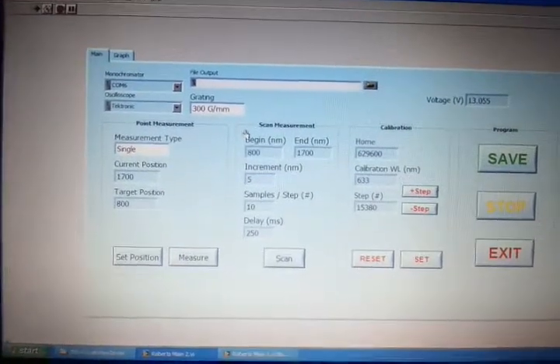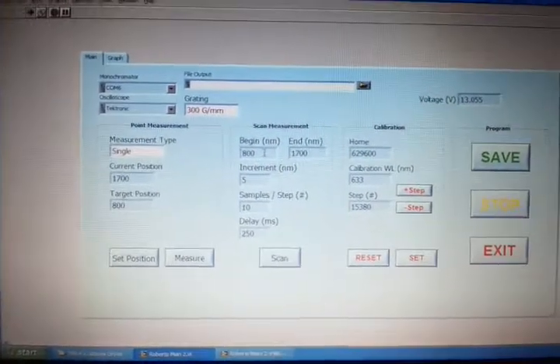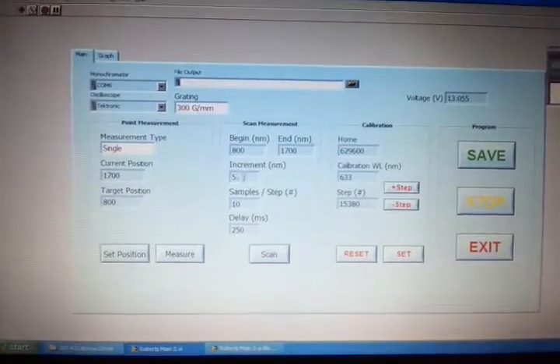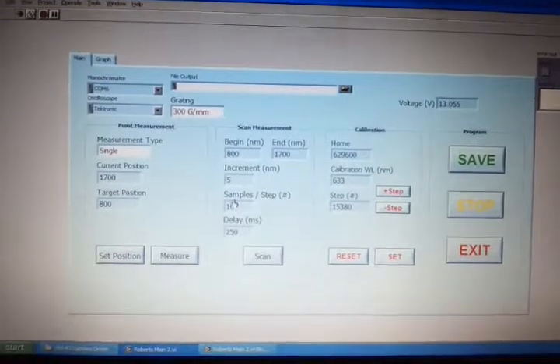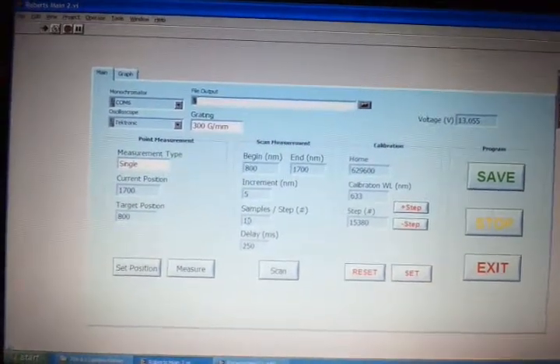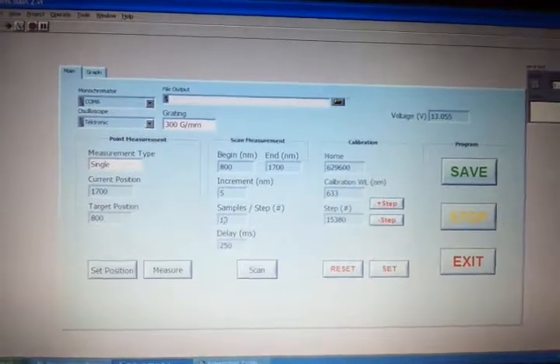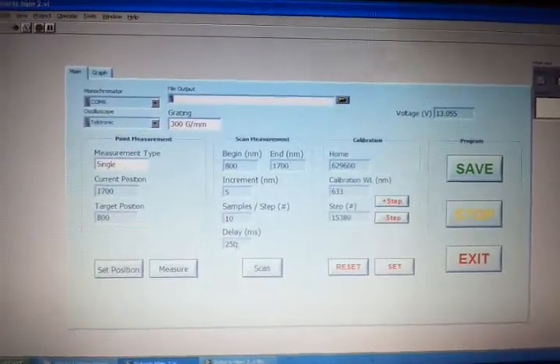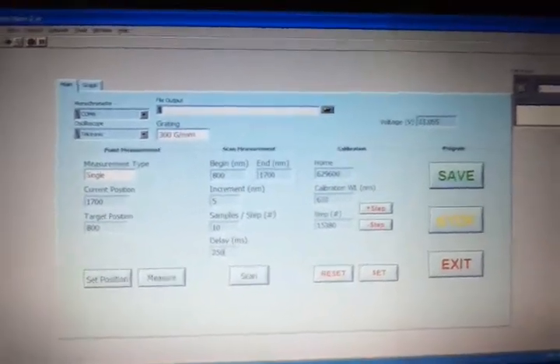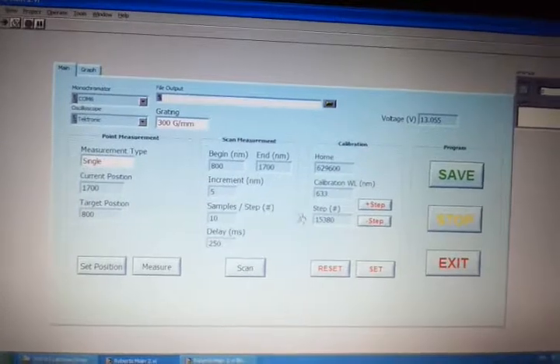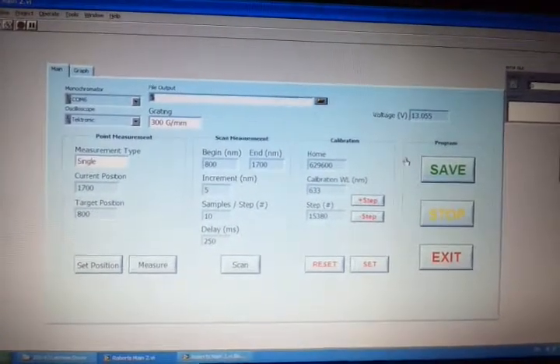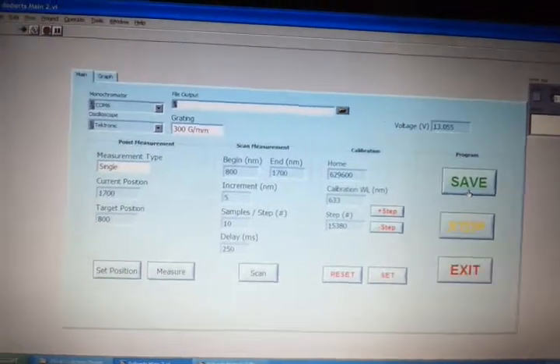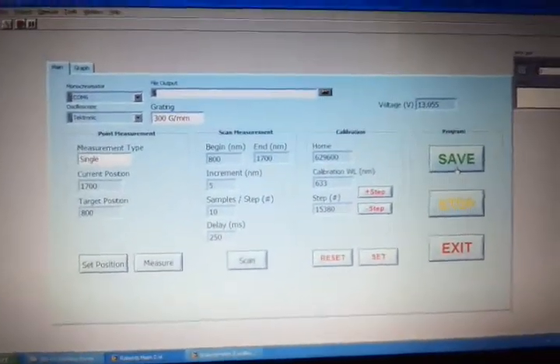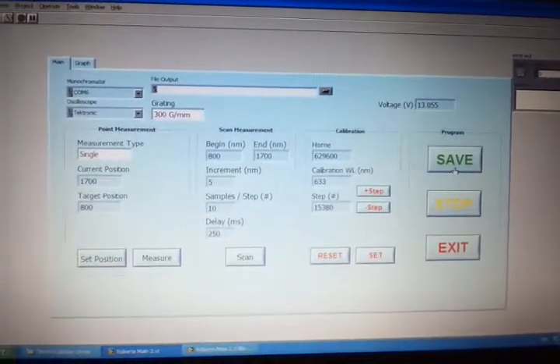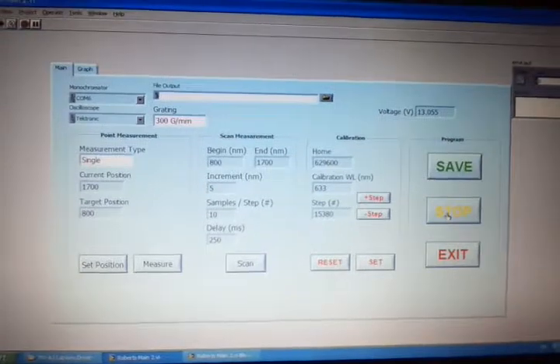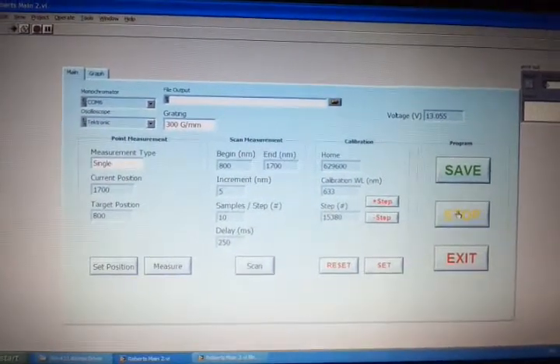If you want to do a scan measurement where you scan between wavelengths, set your beginning here, your end here, your increment between steps, how many samples you take to average over for each step to obtain a resultant voltage from a current, and then the delay to give the electronics time to settle. After you're done with the measurement, you can click Save here. A prompt will come up to give you a location to save the text file that has the wavelength and the corresponding voltage. If at any time you wish to stop what you are doing, you can click Stop.